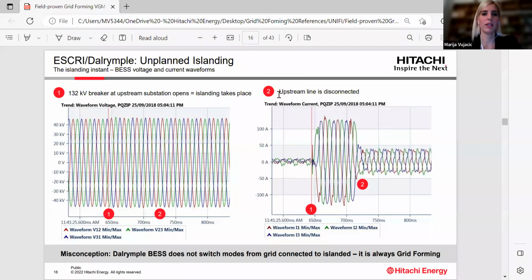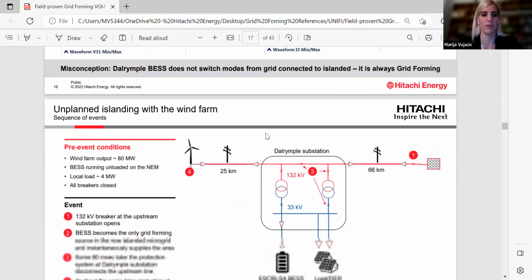What is again important to highlight here is that all the time in ESCRI the system is running as grid forming. There was no transition from grid following to grid forming and then vice versa. All the time the system is operating in grid forming.